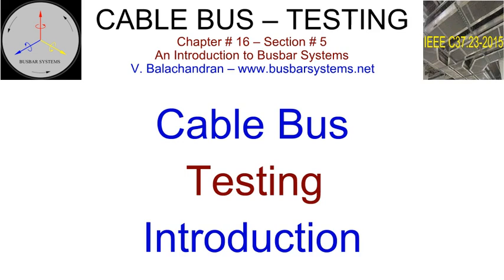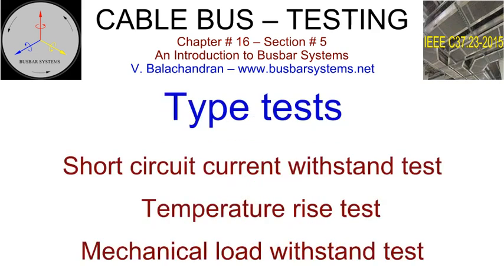The testing of the cable jointing/terminating kits is not in the scope of the cable bus supplier. They shall be tested and certified as per the relevant applicable standards for cable accessories. The following type tests need to be performed on a cable bus to verify the design for a given configuration. Short circuit current withstand test. Temperature rise test. Mechanical load withstand test.